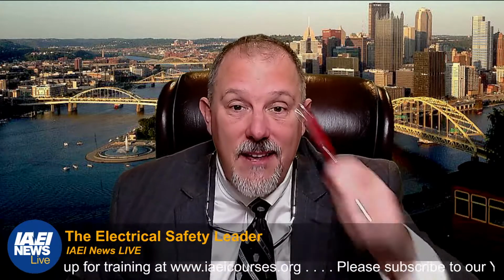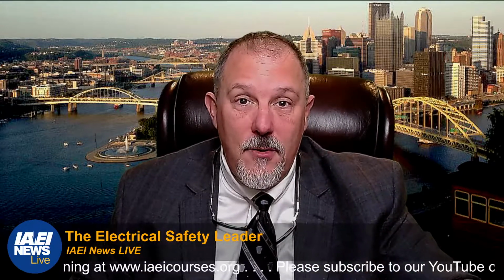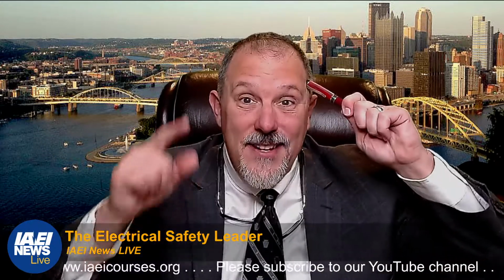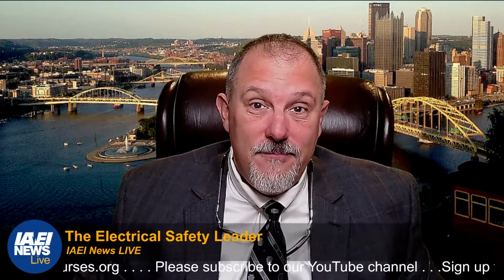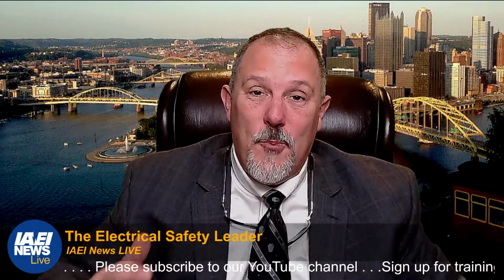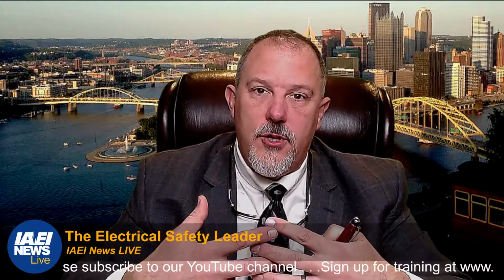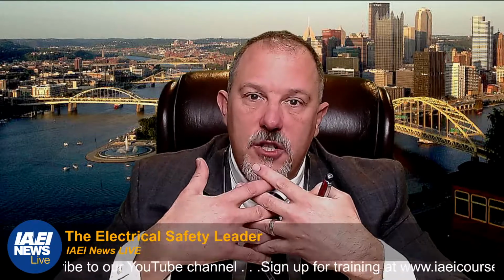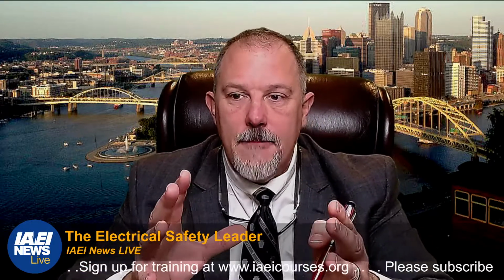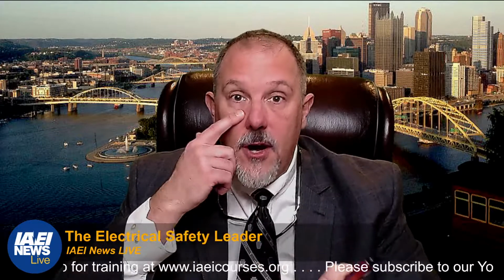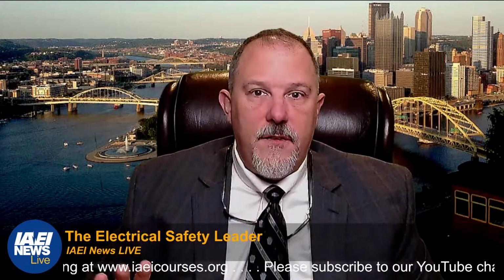I've got my Keith Laughlin thinking pen, and I'm telling you, even Keith might say that to you. You've got to open the doors, you've got to expose the conductors, you've got to expose your terminations, because you need to be able to see the heat in that specific area, not the heat of the entire front of the enclosure.